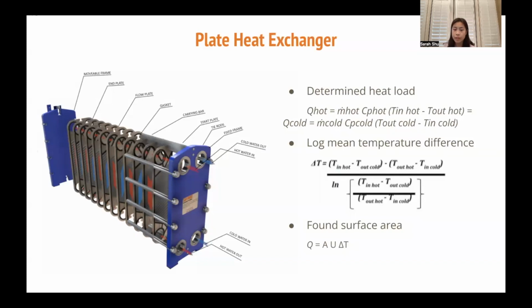To know the total heat load to be removed, the amount of ice was determined using the density of water. The heat gained through convection was calculated through the difference in temperature between the air above the ice surface and the indoor temperature of the rink. It was calculated that the cooling system would need to remove approximately 1,200 kilowatts to keep the ice at the same temperature and state. Knowing this information, the dimensions of the plate heat exchanger were calculated.